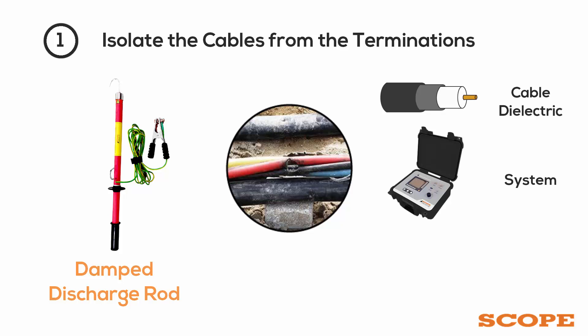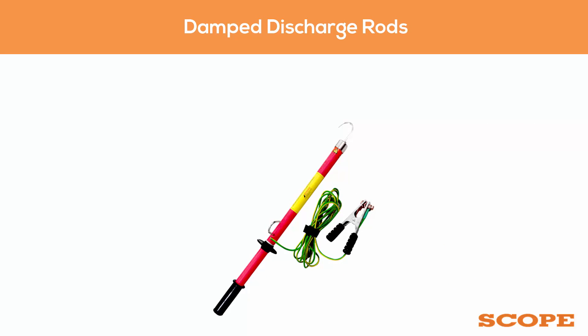When a cable fault happens, the first step is to isolate the cables from the terminations. Discharging the residual charge present on the cable after switching off the line requires damped discharge, for safety of cable dielectric and the system as well as the operating staff. Scope offers damped discharge rods as per the voltage level of the cable.